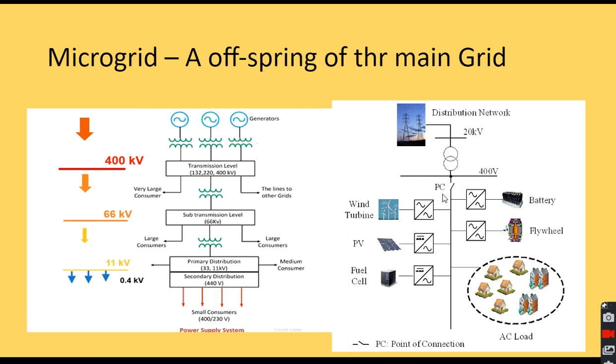This is the point of connection where it links to the distribution network, maybe at 0.4 kilovolt distribution voltage. If there's excess power, you can connect it to the distribution network itself, but the voltage has to be stepped up first. That's why there's a transformer here connecting to the distribution network, which will be around 20 kilovolt, or 11 kV, 22, or 33 kV.